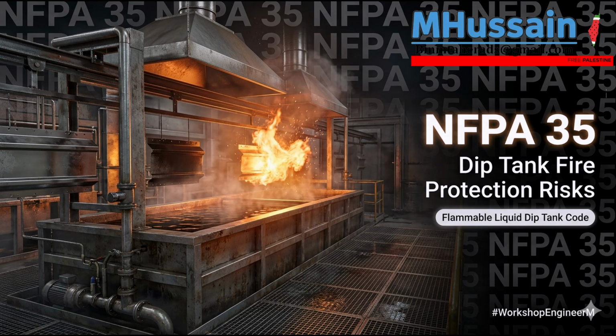Wow. So if a facility has a basement, that subterranean space acts as a massive, invisible collection basin. A completely silent trap. Exactly. A relatively minor spill on the operating floor could result in a basement that is completely saturated with an explosive vapor-air mixture. Without anyone even knowing. Exactly, because basements generally lack natural cross-ventilation. So the vapor just sits there waiting.